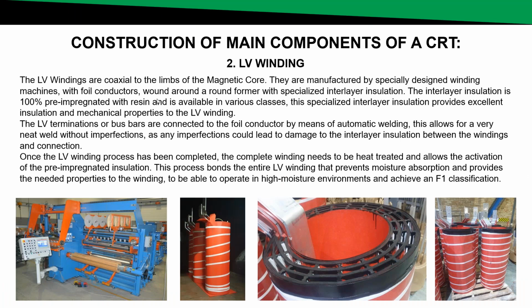The LV winding is always fitted coaxial to the limb of the magnetic core. They are manufactured using very specialized equipment, specially designed to wind cast resin transformer LV windings. These LV windings are usually manufactured in a round shape by using aluminium foil and 100% pre-impregnated interlayer insulation.